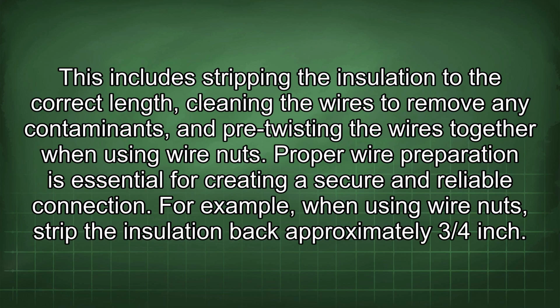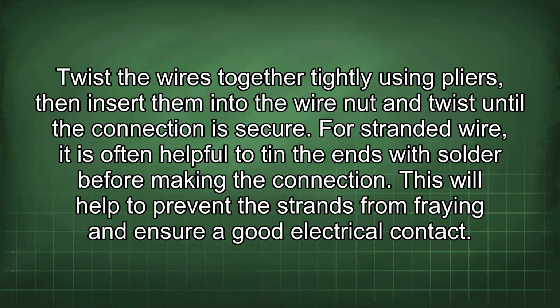This includes stripping the insulation to the correct length, cleaning the wires to remove any contaminants, and pre-twisting the wires together when using wire nuts. Proper wire preparation is essential for creating a secure and reliable connection. For example, when using wire nuts, strip the insulation back approximately 3/4 inch. Twist the wires together tightly using pliers, then insert them into the wire nut and twist until the connection is secure. For stranded wire, it is often helpful to tin the ends with solder before making the connection. This will help to prevent the strands from fraying and ensure good electrical contact.